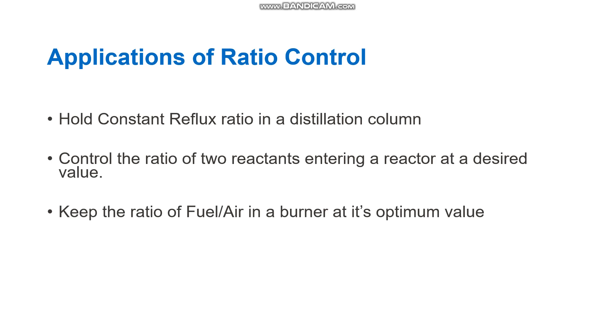There are many applications of ratio control. It is used in a distillation column to hold a constant reflux ratio. It is also used to control the ratio of two reactants entering a reactor at a desired value. A very good example is in a boiler, where the fuel-to-air ratio is controlled in a burner to achieve its optimum value.